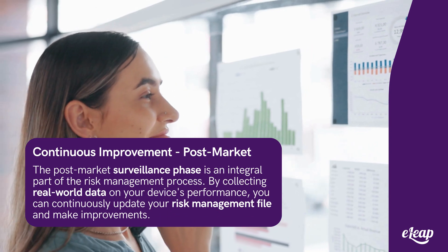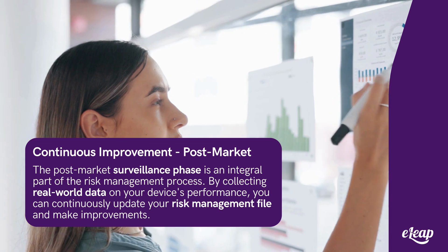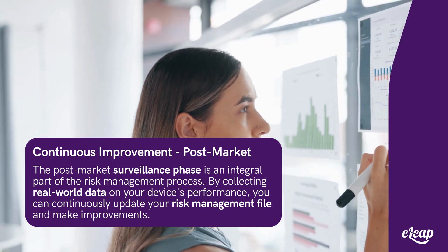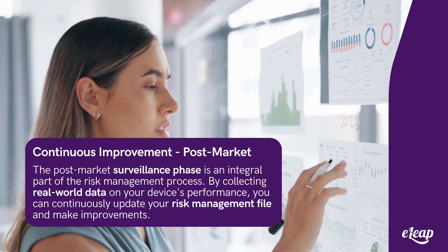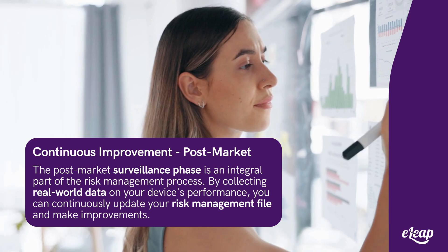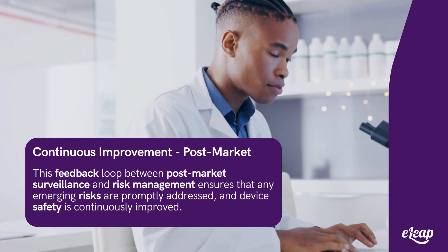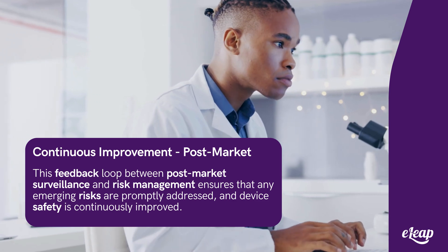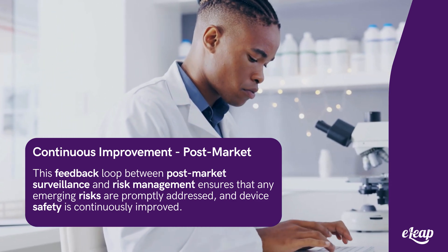The post-market surveillance phase is an integral part of the risk management process. By collecting real-world data on your device's performance, you can continuously update your risk management file and make improvements. This feedback loop between post-market surveillance and risk management ensures that any emerging risks are promptly addressed and device safety is continuously improved.